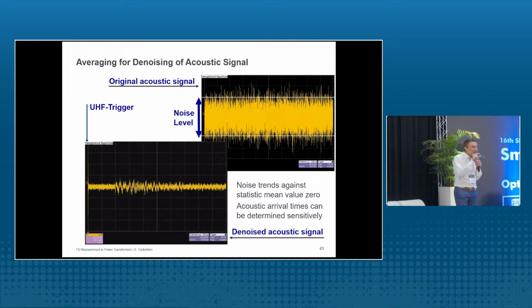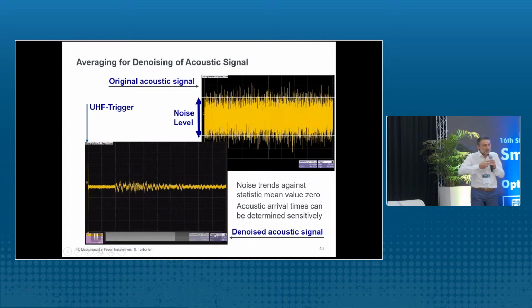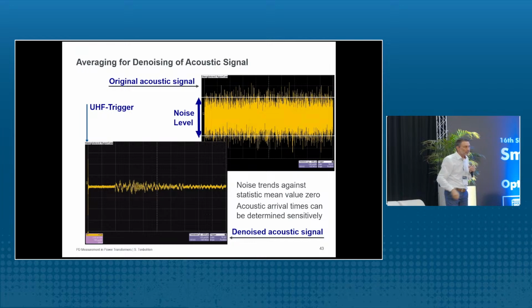Yeah, this is more or less just noise, because the signal itself is so small. But we can use the UHF sensor as a trigger source. So we trigger the acoustic measurement by the UHF, and then we average a lot of signals, because with averaging you can reduce the noise. Yeah, and here we have now, let's say 100, 150 measurements averaged. Due to this average, the noise is decreased. You can see here the noise. And here now you can see also the acoustic signal, which is coming out of the noise due to the averaging. So we used, in this case, UHF for triggering the acoustic measurement. And then we have here, of course, the traveling time of the acoustic wave inside the transformer tank. And if you do this in different positions, you can calculate the origin of the PD.